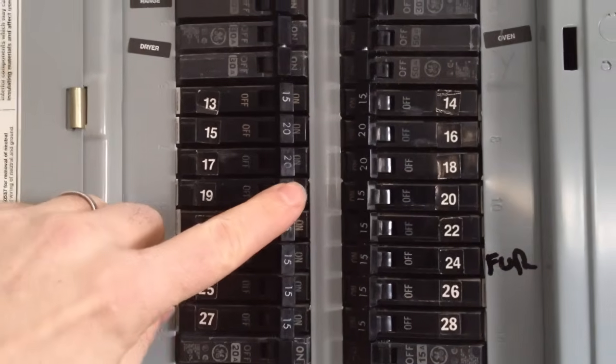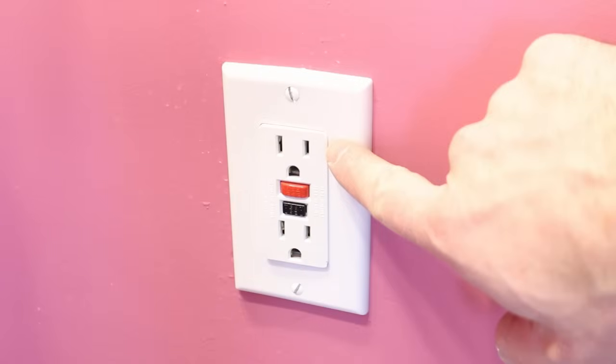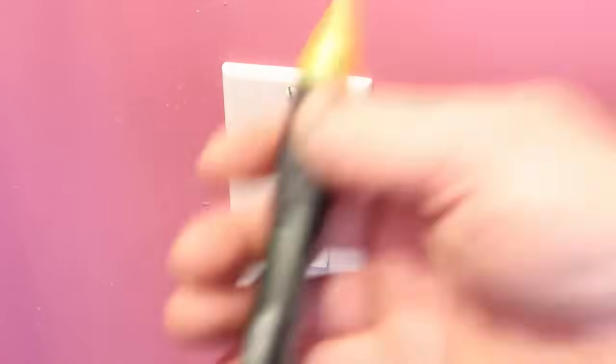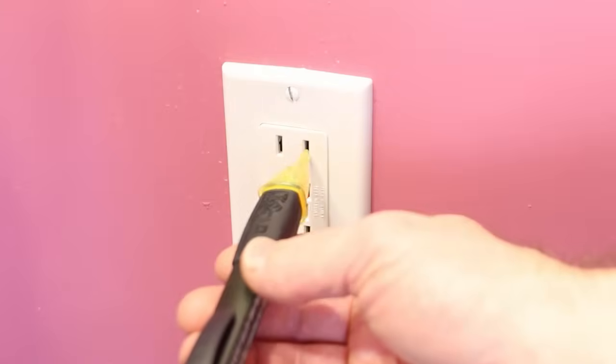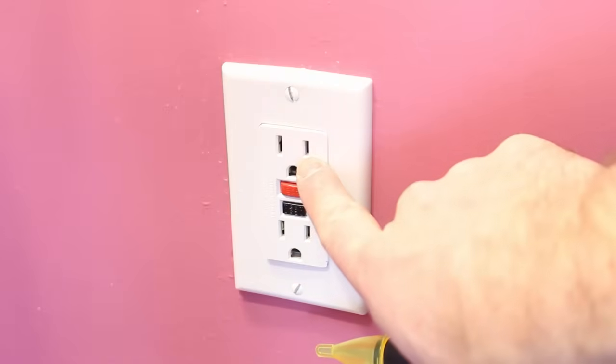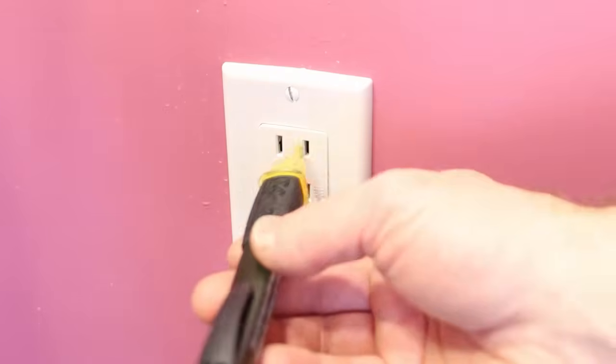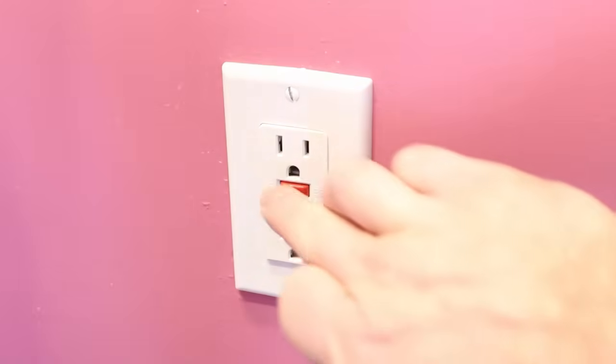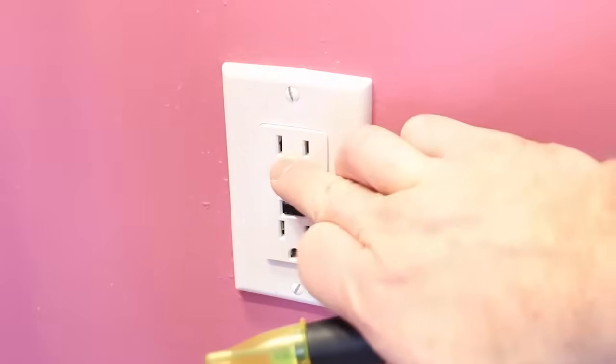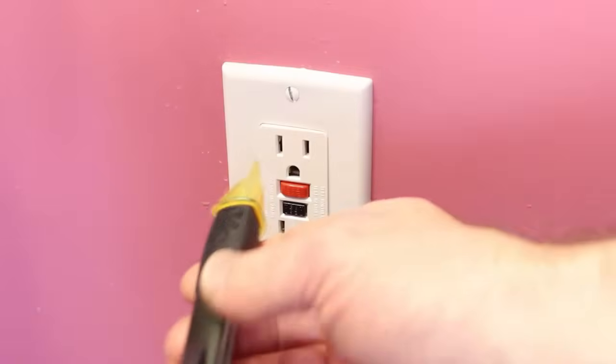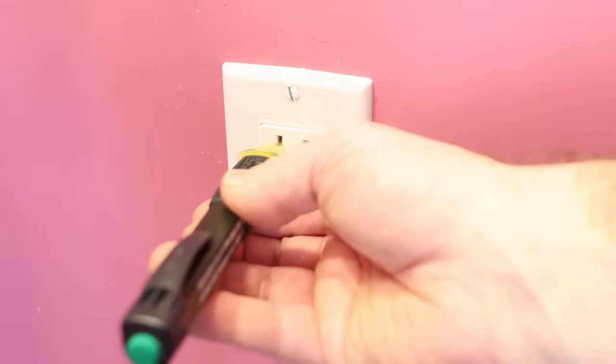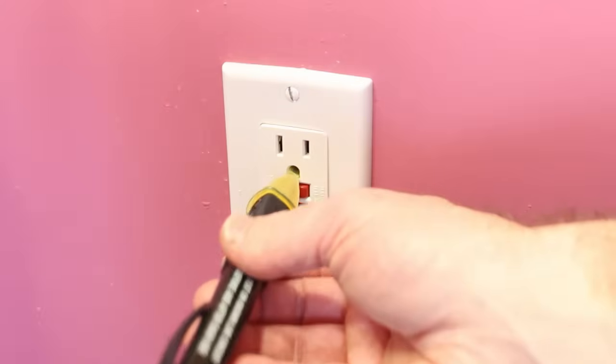Now you can go ahead and turn off the power at the circuit breaker. Once the circuit breaker is turned off, test the outlet again using your voltage detector. Stick the voltage detector into the hot slot, which is the short slot. Then just to double-check in case somebody wired this outlet incorrectly, test the neutral slot and the ground slot.